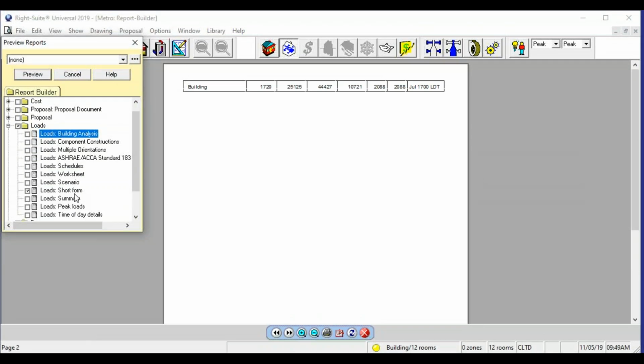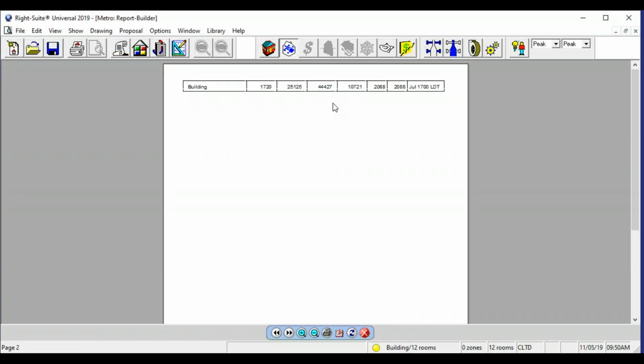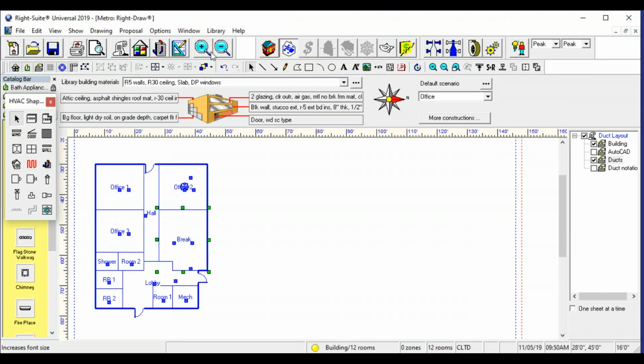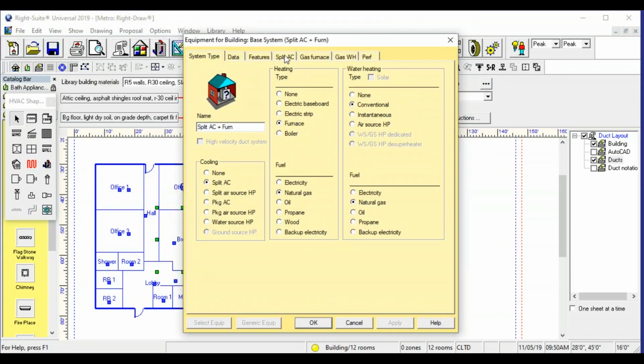I always like to look at loads in the short form, and then I'll take a look at my BTU amounts that I have here. Now remember, we got our square feet of 1,720. That's our heating, and this is our cooling. So we're at 44,427 BTUs for the sensible, and our latent is at 10,721. So right there I can tell you we're within a 5-ton range, and so we're going to go ahead and roll on that. So let's go ahead and choose the equipment.